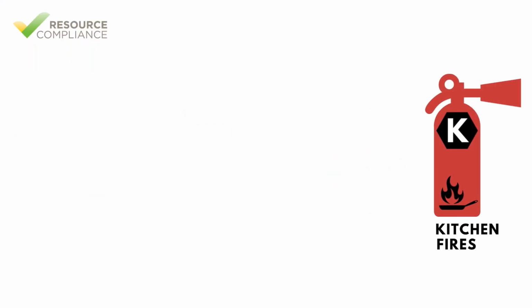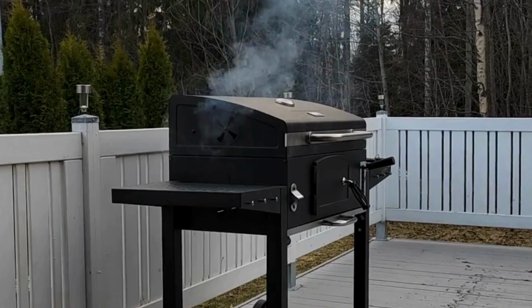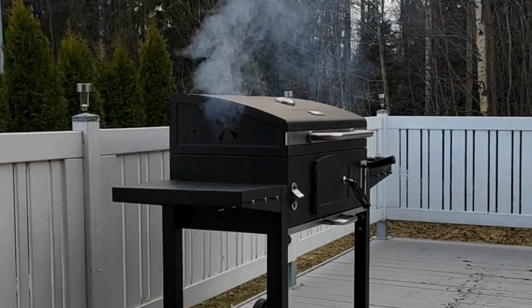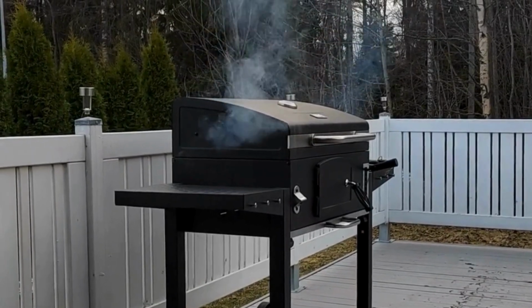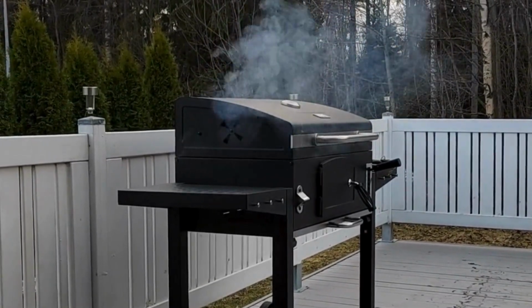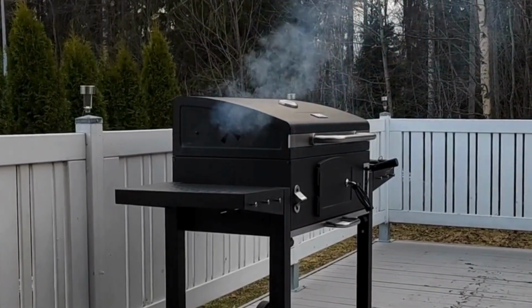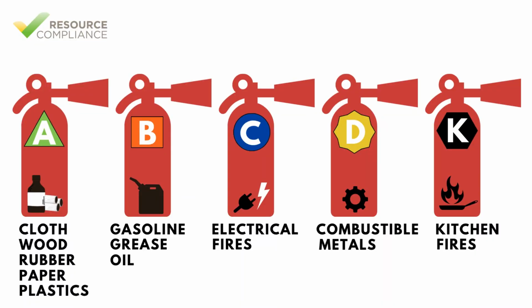Class K designates fires involving commercial cooking appliances, animal fats, and vegetable oils. The extinguishing agents for Class K fires are wet chemical agents that cool and form a foam blanket over the oil. Class K extinguishers have a black hexagon with a K inside.